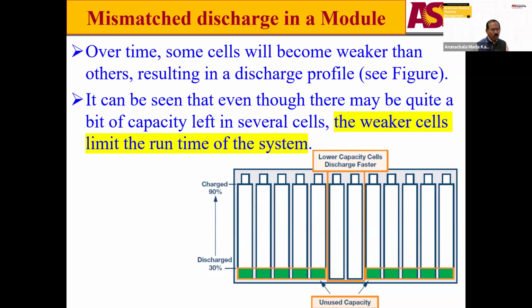The current through the module is exactly the same, so the same current goes through all the cells. Now the load will still operate because the load has an operating voltage range. So with the 2 cells showing lower voltage, the module voltage may not stop the load from operating. This is a situation that could happen with the mismatched or weakest cell during capacity discharge.